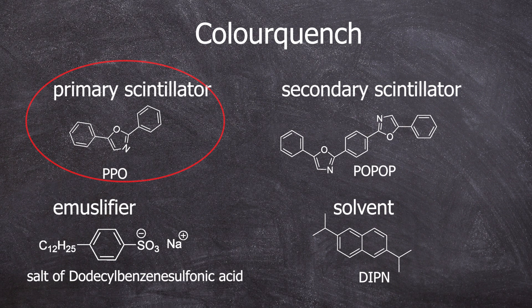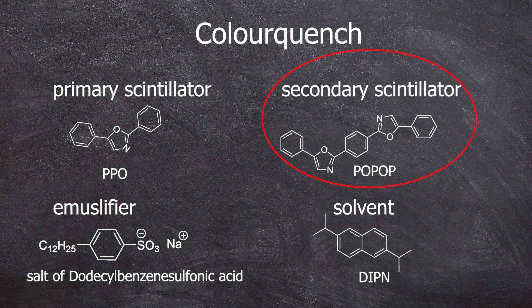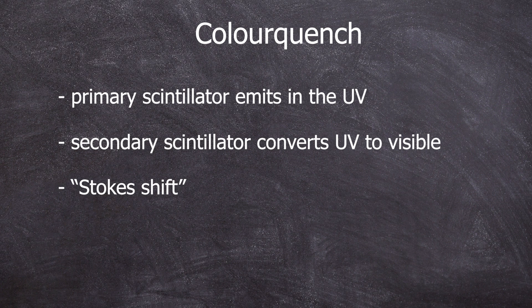And then there is the color quench. I mentioned a few minutes ago that the scintillator emits in the UV range. That's bad if the photomultiplier has an absorption maximum in the visible range. Therefore, there is a secondary scintillator in the cocktail. The secondary scintillator or wavelength shifter ensures that the photons emitted by the primary scintillator fall within the correct wavelength range for the photomultiplier. Stokes shift is the technical term for this.